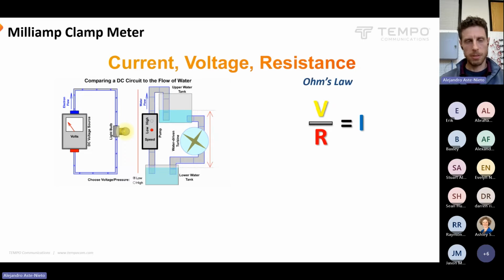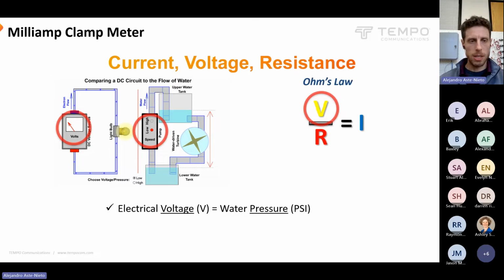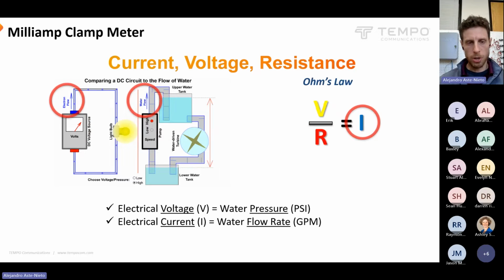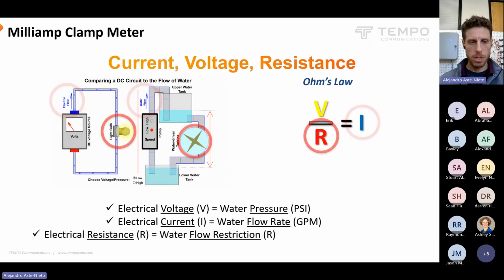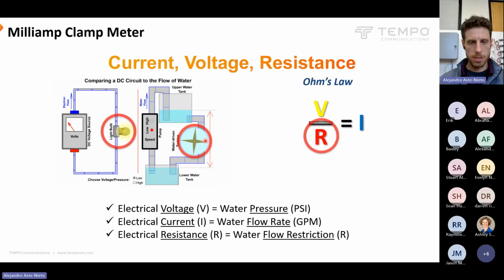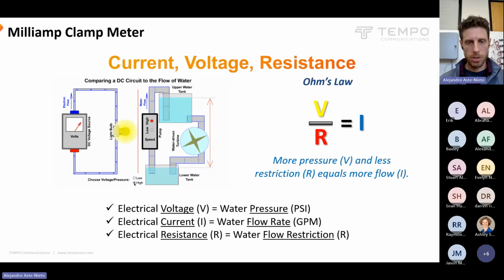So just to revisit the concept of Ohm's law with current, voltage, and resistance, keep in mind that voltage is like electrical pressure. If you think of this water system with a pump, the pump is what's providing the voltage or the pressure. The electrical current, which is what we're measuring with the clamp meter most of the time, is like the flow rate of electricity, and it's a lot easier to think of in terms of water, right? With more pressure, the more quickly water will flow, and then the resistance is the restriction on that flow. So again, the more pressure and less restriction there is, the more flow. The amount of current that we measure tells us a lot about what's going on out there.